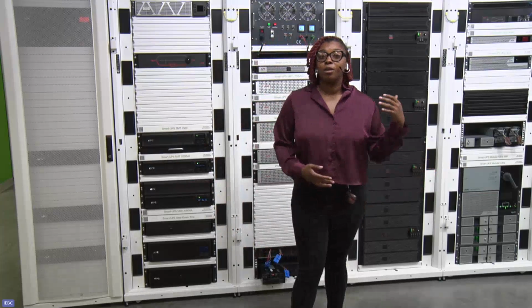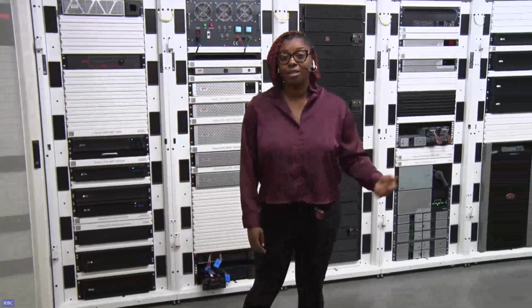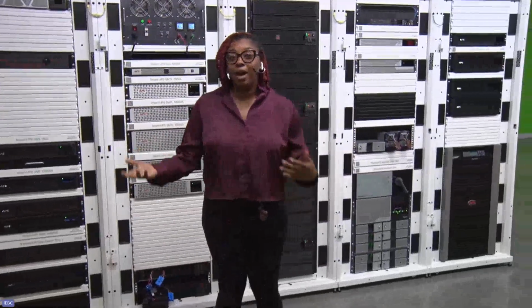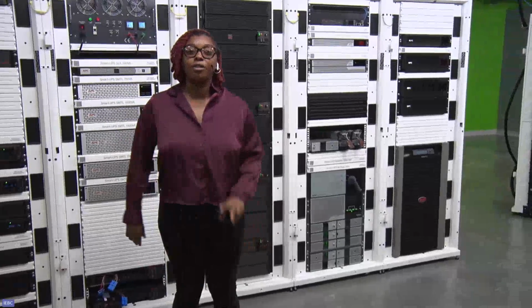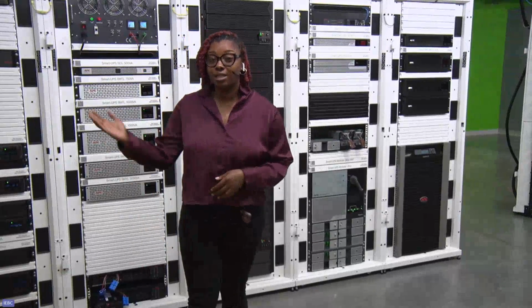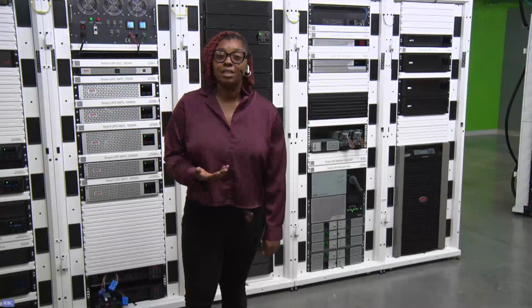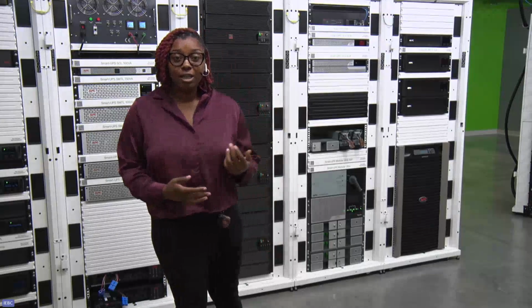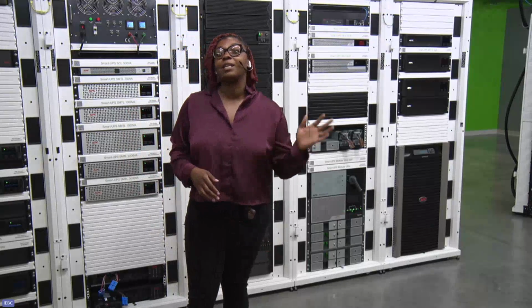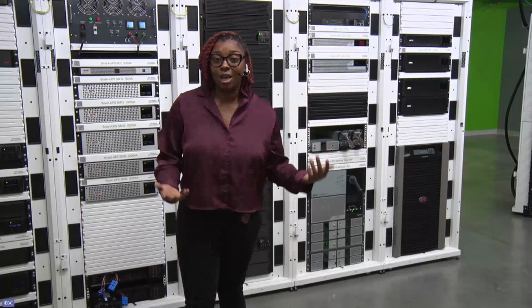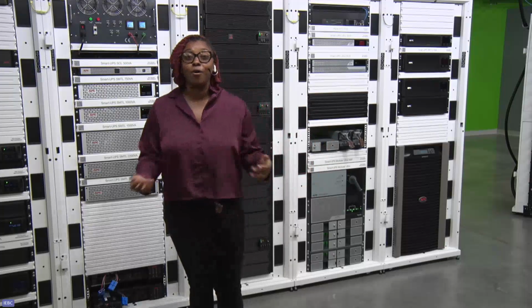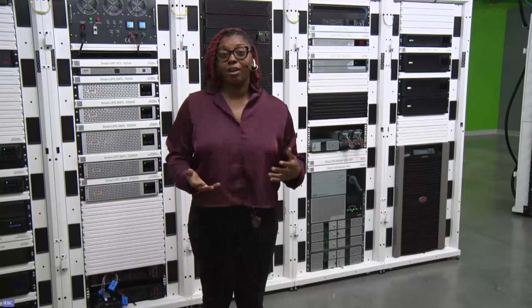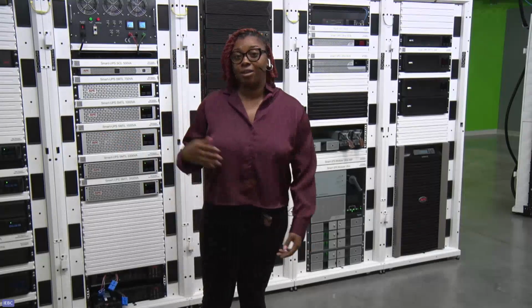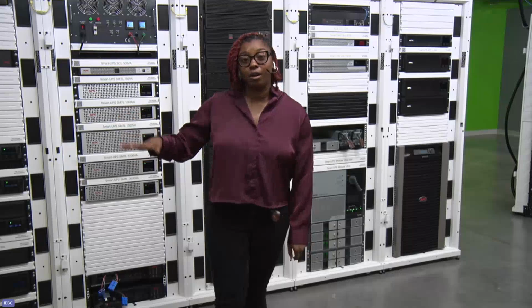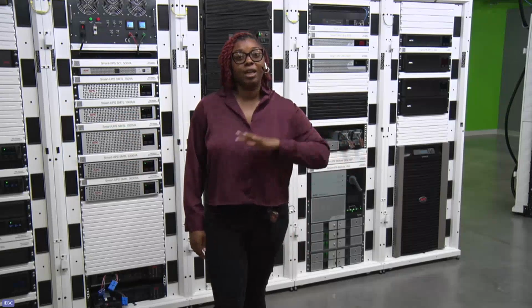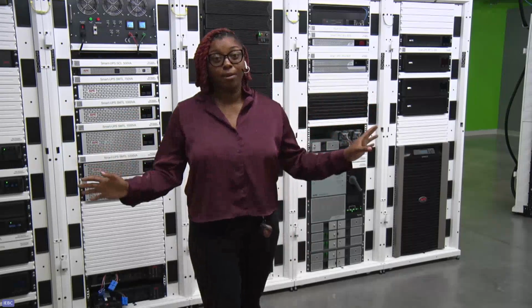Turning to a double conversion UPS: you have the same incoming AC power, that same sine wave, but two conversions happen. You go from incoming AC power, convert it to DC power, do some power conditioning, then do a second conversion from DC back to AC. So this type of UPS system creates its own sine wave, meaning it doesn't really care if the incoming power is good or bad. Line interactive just cleans up small anomalies; double conversion creates its own sine wave regardless of what's coming in.